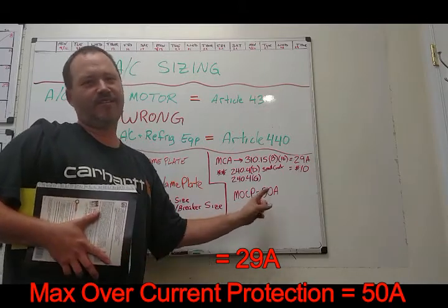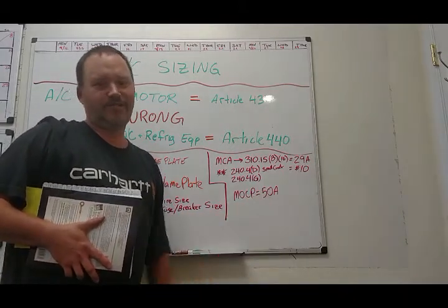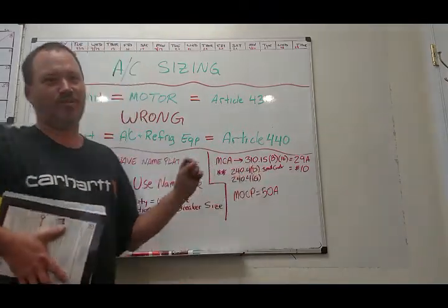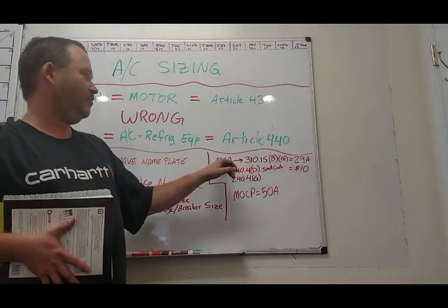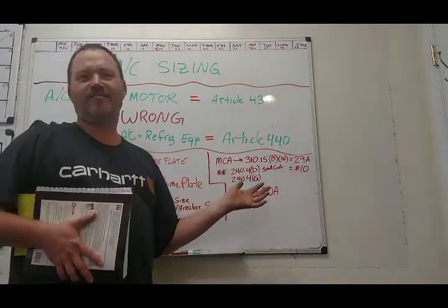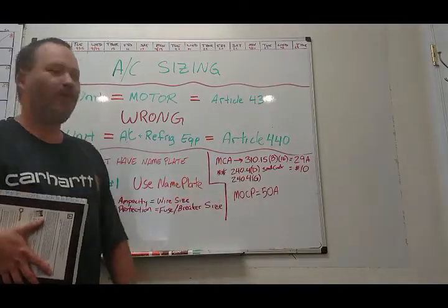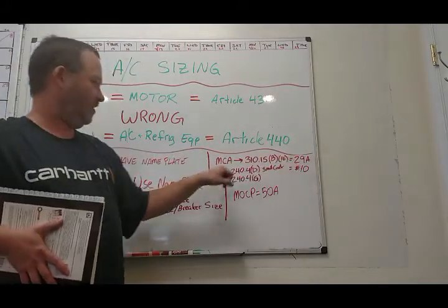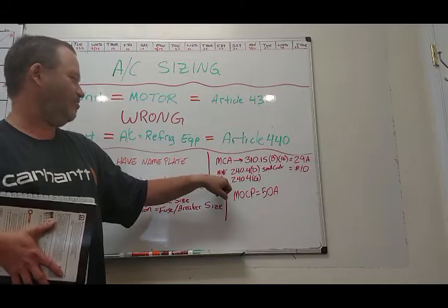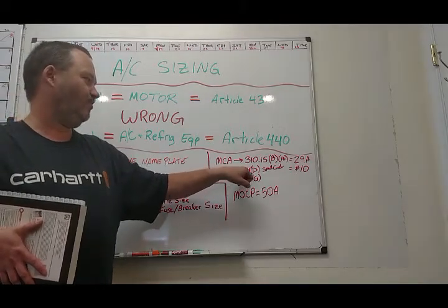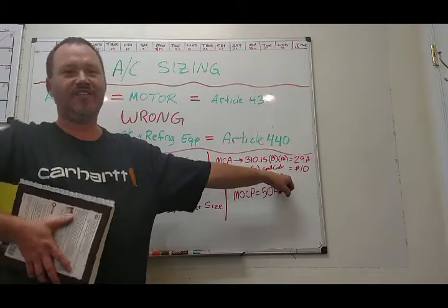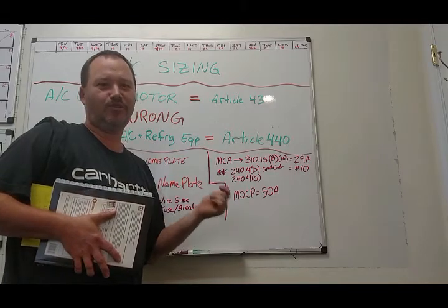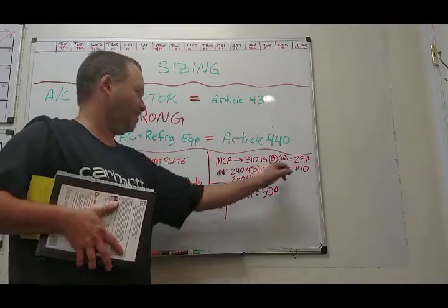The guys out there saying my inspector won't allow that, they probably just don't understand the code all the way. Another thing that guys are arguing about frequently, because on the small residential units, it'll say the minimum circuit ampacity is something like 25 amps, 24 amps. And a guy will say, put number 12 on it. Everyone goes to Table 310.15(B)(16). At the bottom, there are the two asterisks that we all see, and everybody knows about them. That takes you to 240.4(D), the article about small conductors. That says, going down the list, among other things, number 12 copper is only good for 20 amps. That is true in that situation.